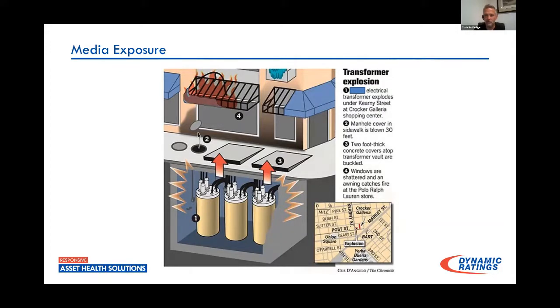The covers on top of the vault were buckled up, and there were some windows shattered, and some fire associated with some of the stores in front of this, which is something else to look at if you're in your town. I would find quite often that businesses would place smoking areas or outdoor patio eating areas very close to or on top of the vault itself. Just another safety thing to take a look at when you're maintaining these networks. Again, the biggest concern with these failures is, of course, the cost of replacement, but it's really a safety issue more than anything.